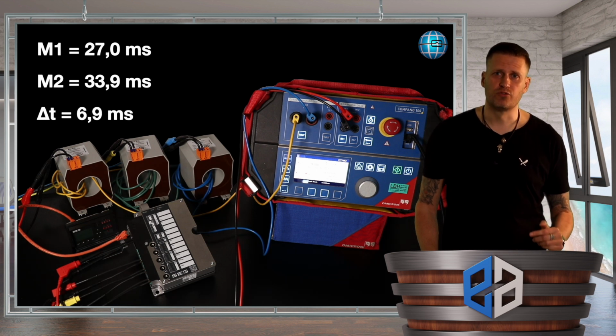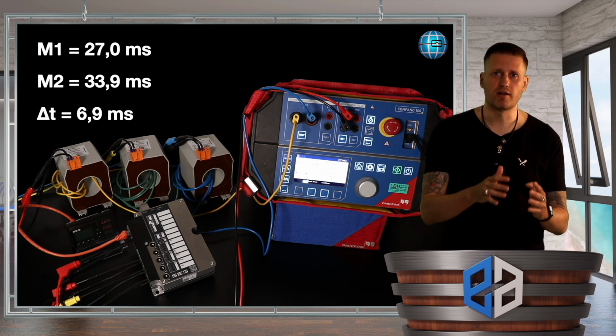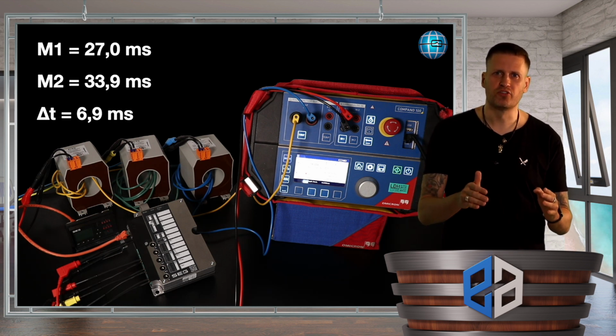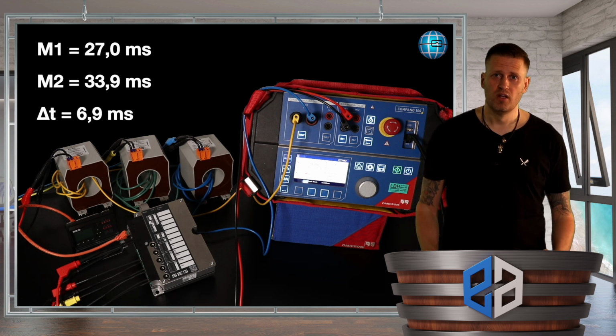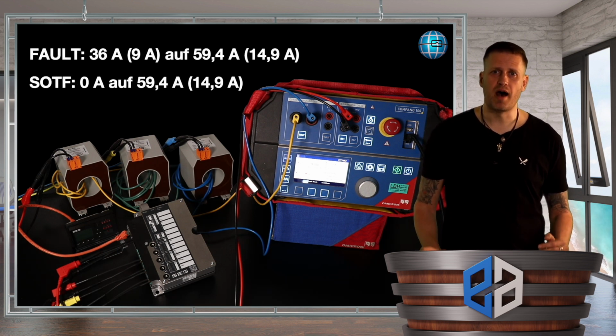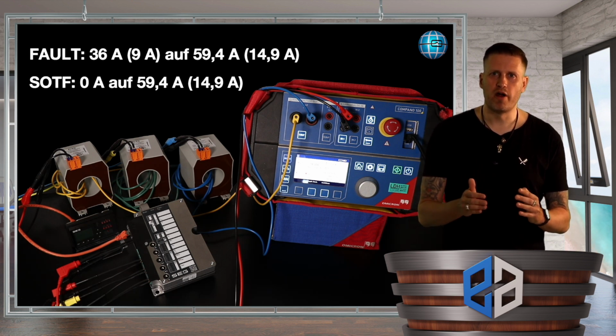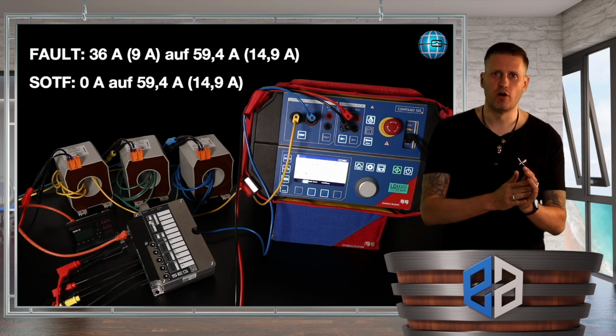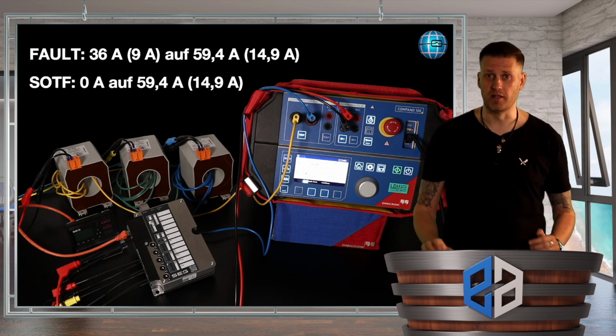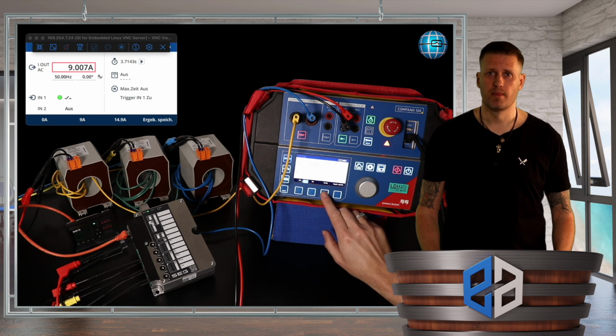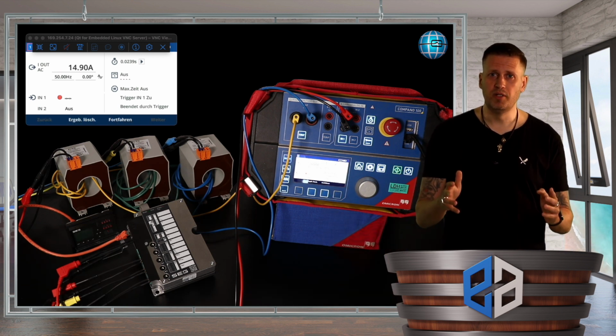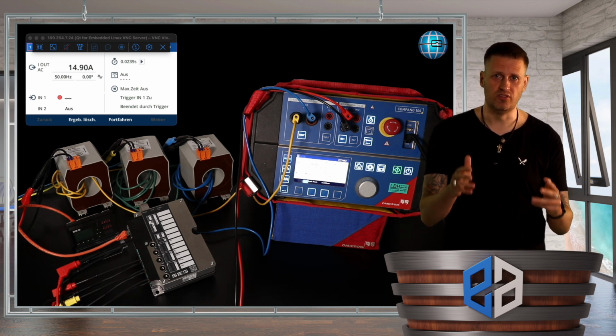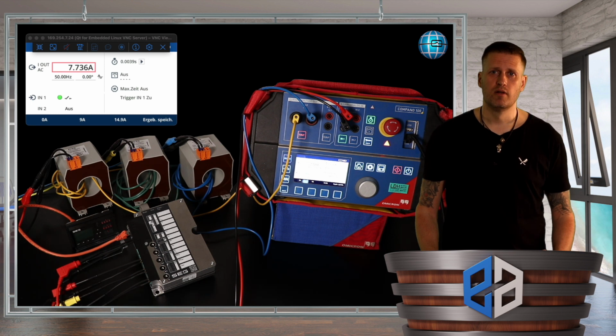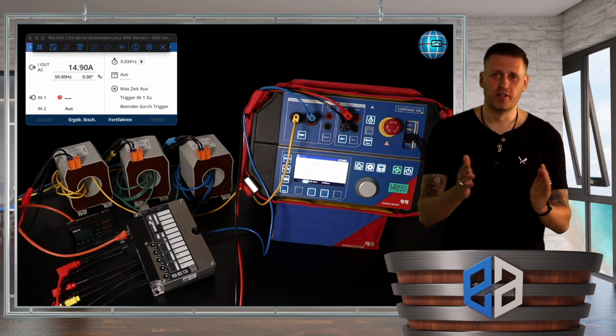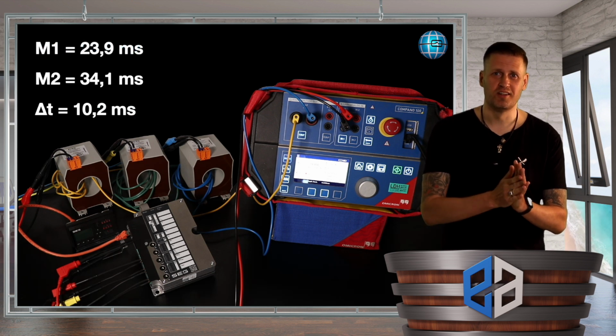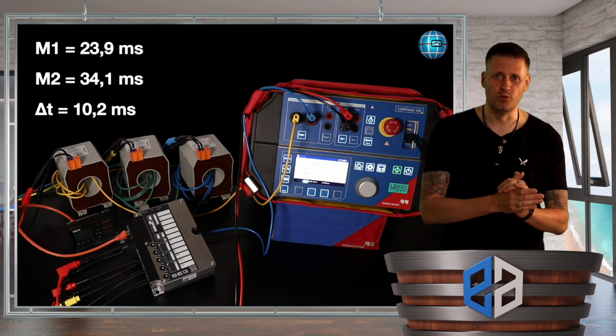Okay, let's take it to the extreme and repeat the measurement with an even smaller current. We now jump to 110% of the parameterized pickup value. This is 54 amps and we are now testing with 59.4 amps, or with the 4-fold winding current of 14.9 amps. We push the button again. Okay, and repeat this test for the second time, coming from 0 amps. And measure an amazing time difference of only 10.2 milliseconds and are ready for the shocking conclusion.